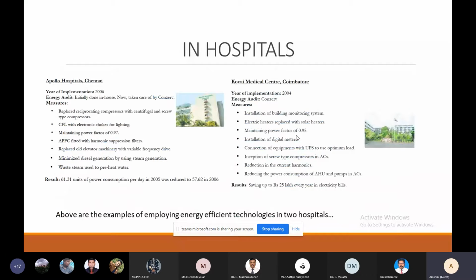This is a case study done by Conserve, an energy audit organization, on Apollo Hospitals in 2006 and Kovai Medical Center in 2004. The measures taken included replacing reciprocating compressors with centrifugal and screw type compressors, replacing fluorescent lamps with electronic chokes for lighting, maintaining a power factor of 0.97, using suppression filters, and using waste steam to preheat water.